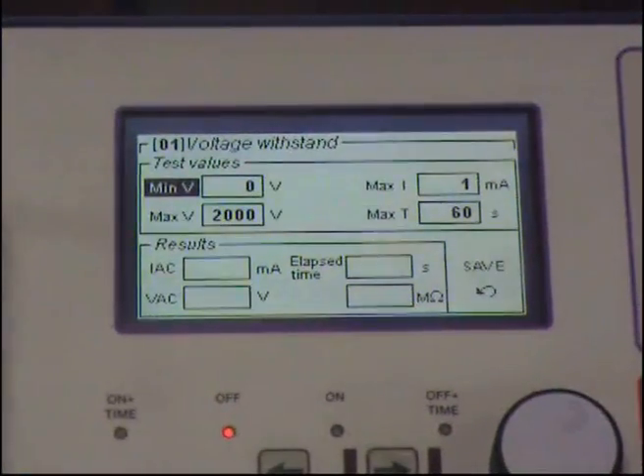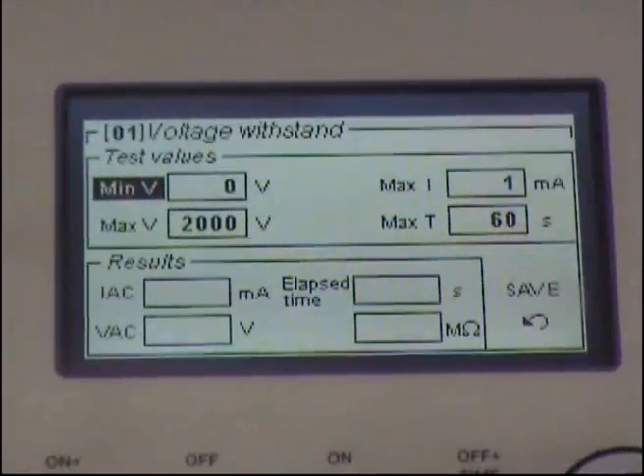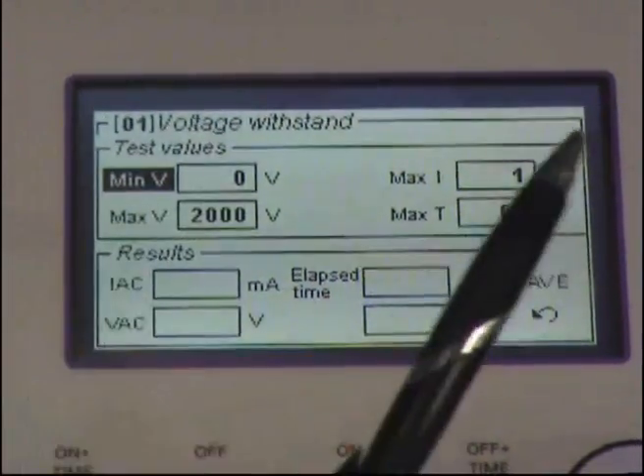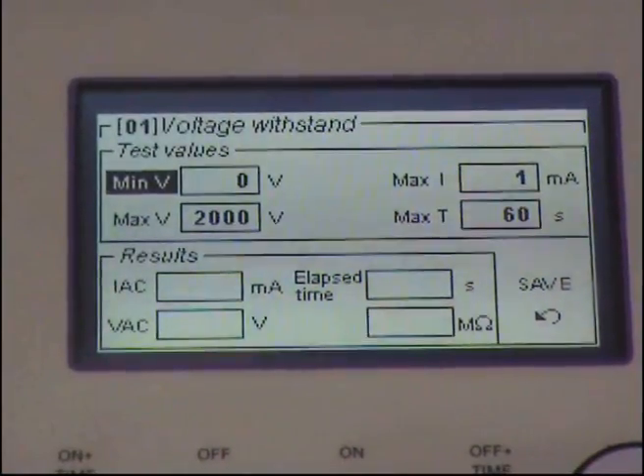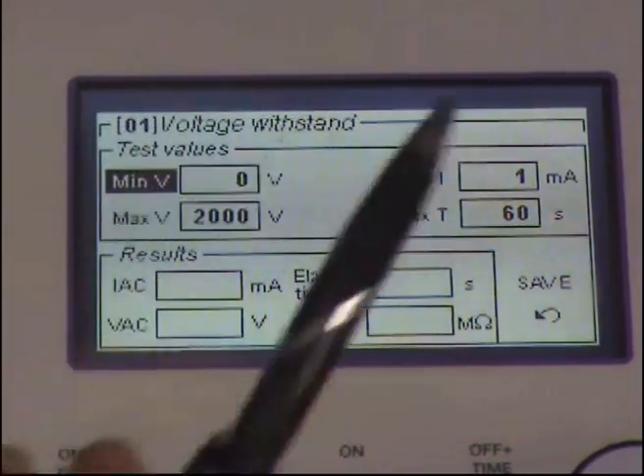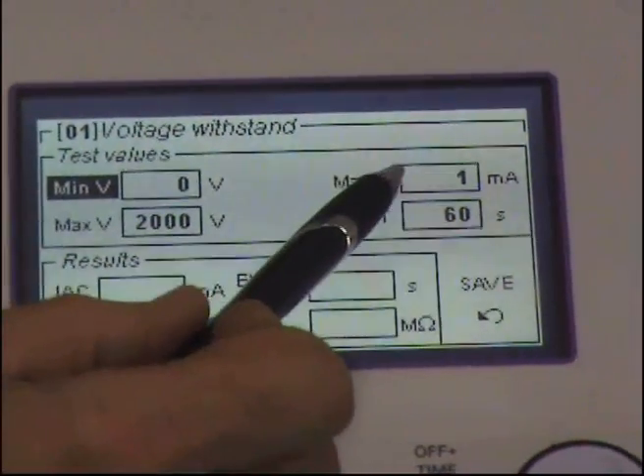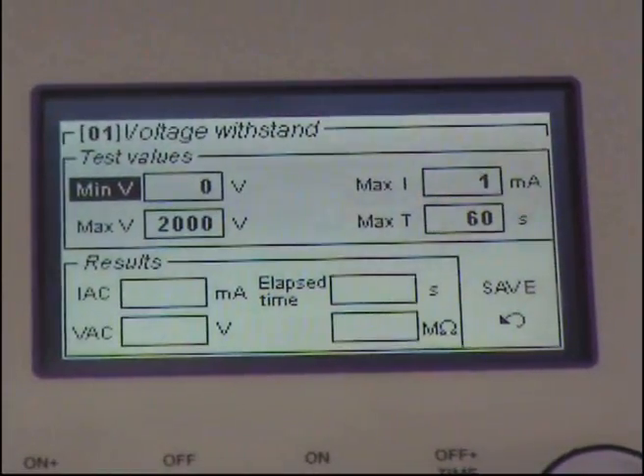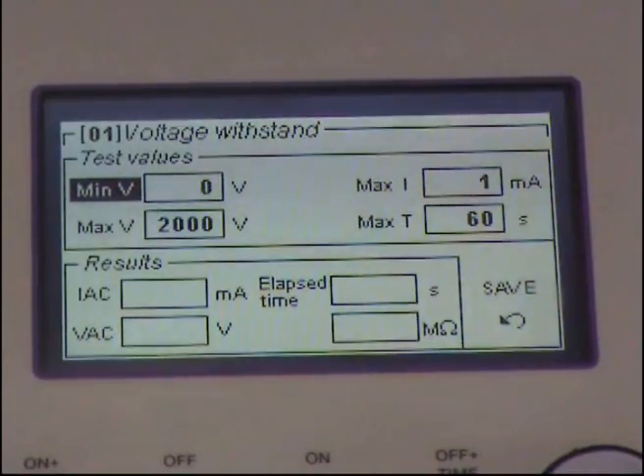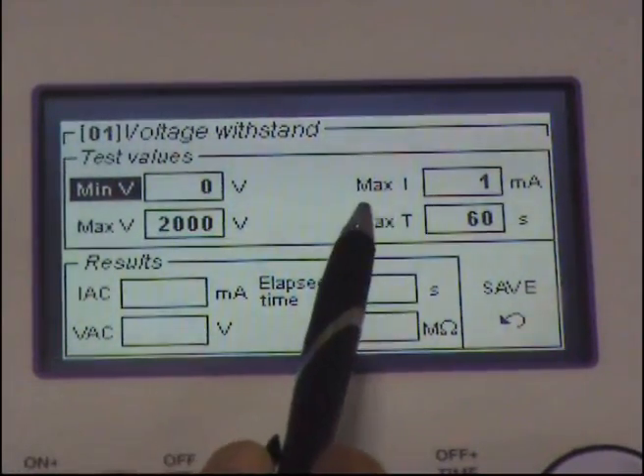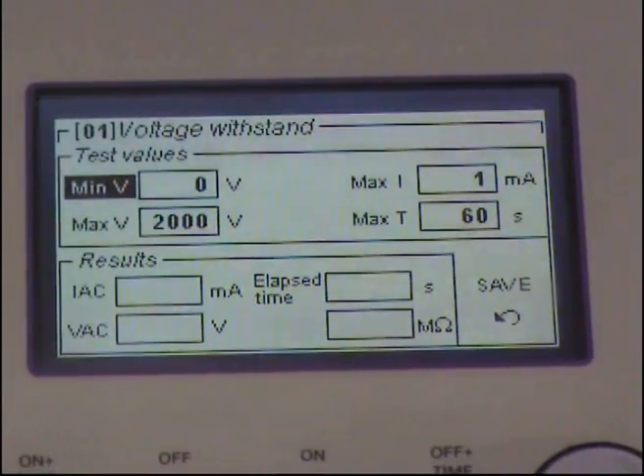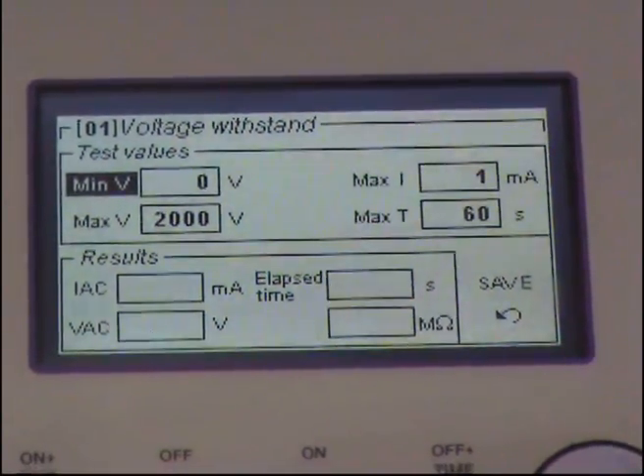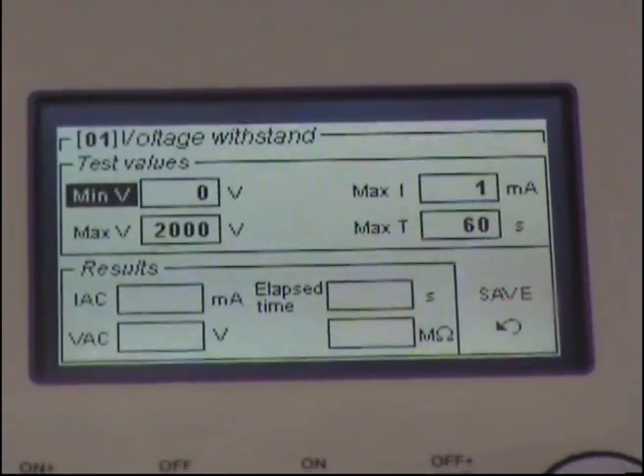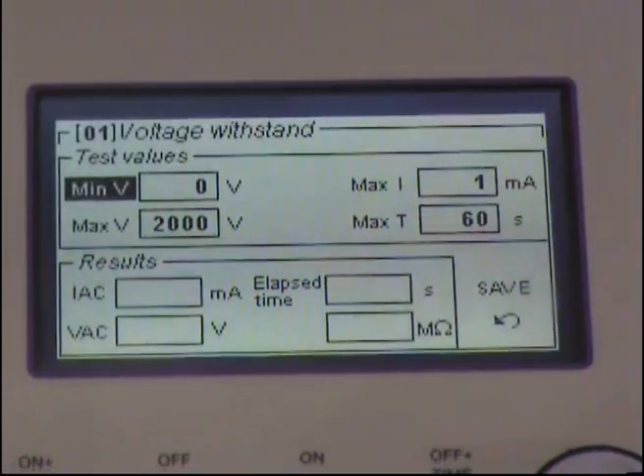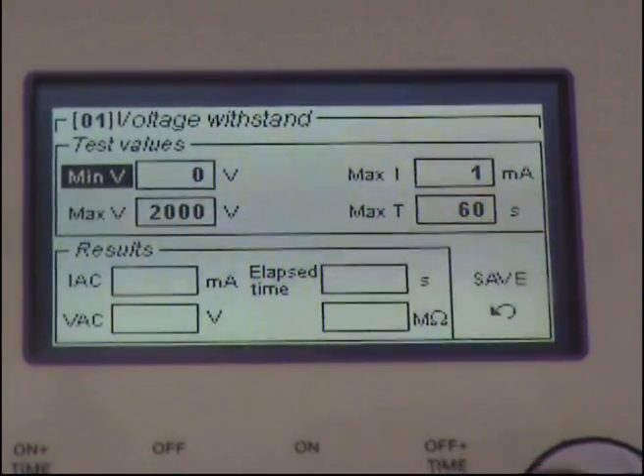So, now what to say? The test values that you can input are the minimum test value, zero, but also the maximum voltage that you want to apply. If you don't want to go beyond 1000 volts, you can program it. And also, this is important, this is the maximum leakage current during your test. Last, the maximum test duration, it is foreseen 60 seconds. If there is no problem during 60 seconds, then the item is correctly isolated. Okay?